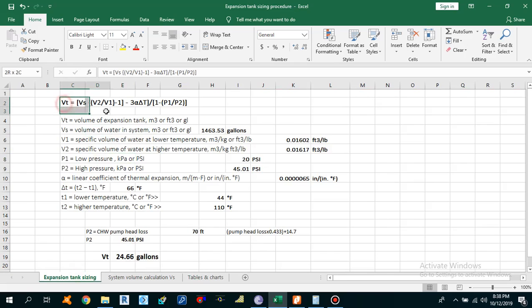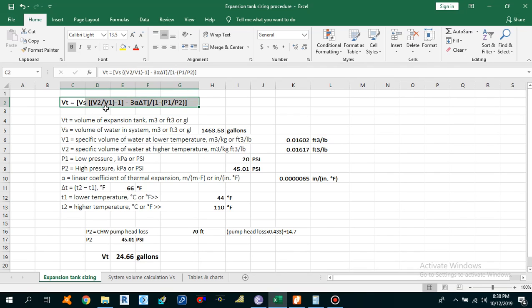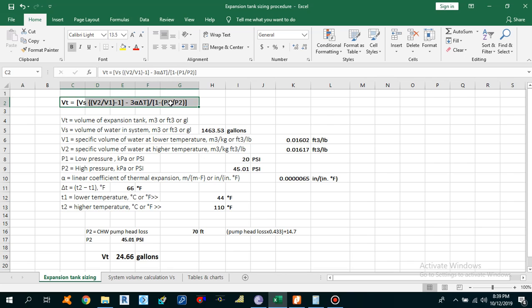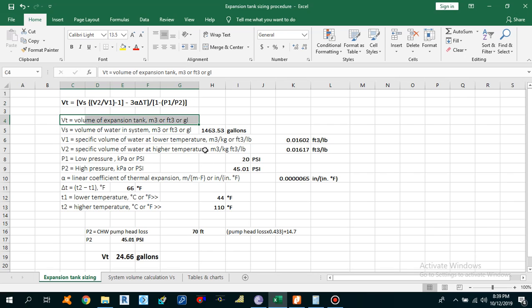This is the formula we are going to use to calculate the Expansion Tank Size: Vt = Vs × (V2/V1 − 1 − 3α·ΔT) / (1 − P1/P2). Vt is the volume of the Expansion Tank, which we are going to calculate in gallons, cubic feet, or cubic meters.